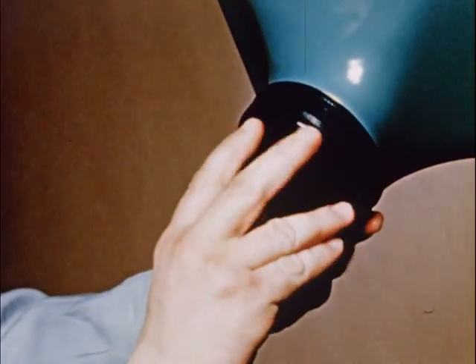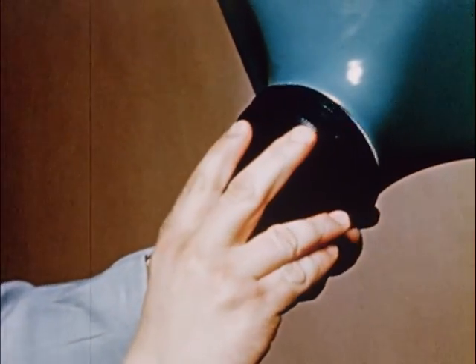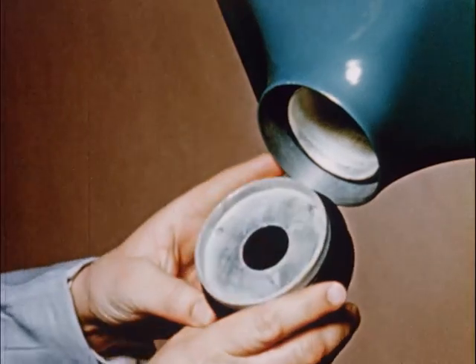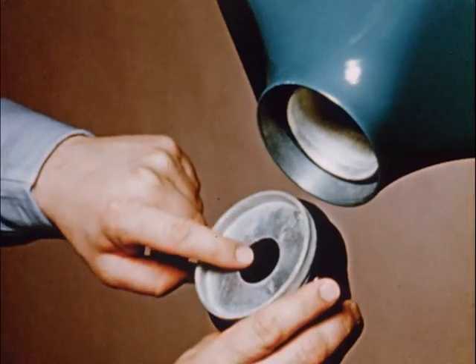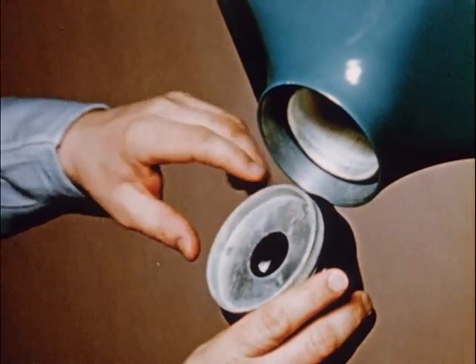The beam of radiation should be confined to as small a cross-section as is consistent with the radiographic requirements. The lead diaphragm, fitted inside the pointer cone, allows radiation to escape only through this aperture, which determines the size of the primary beam.